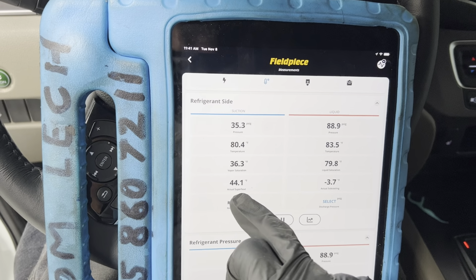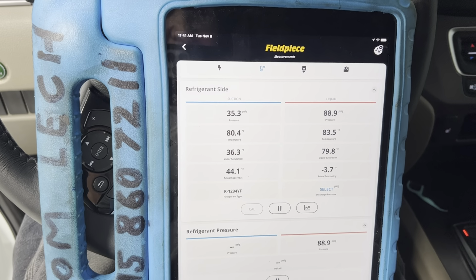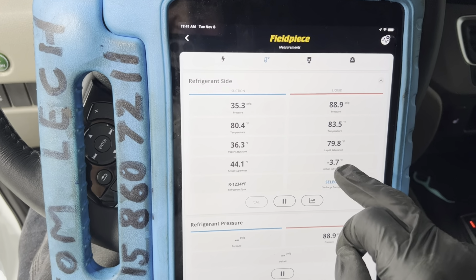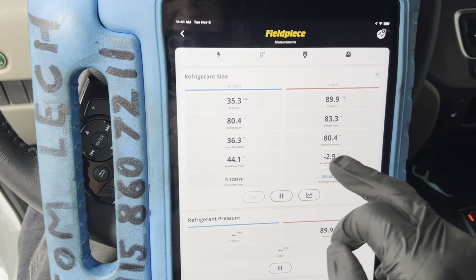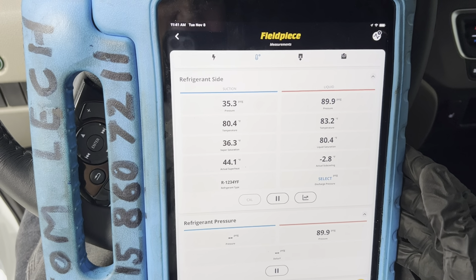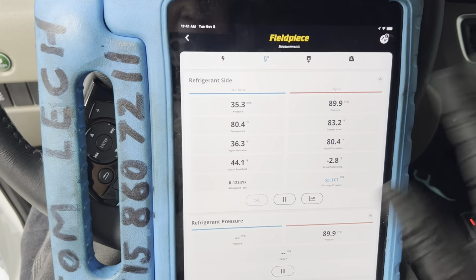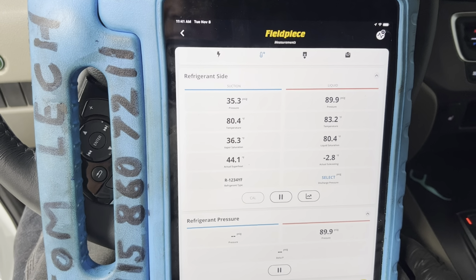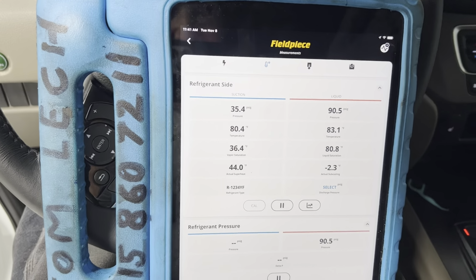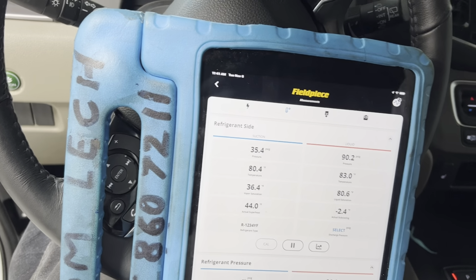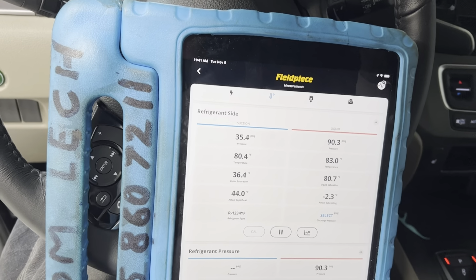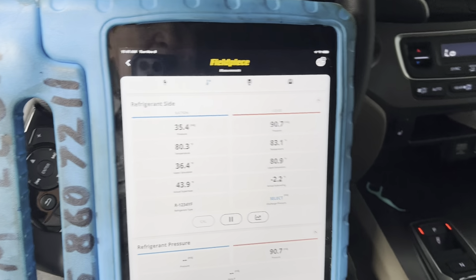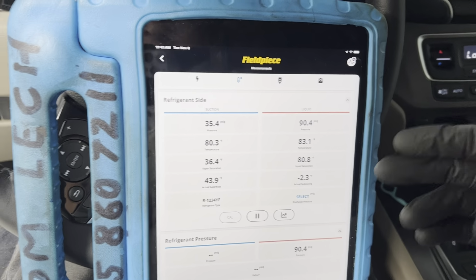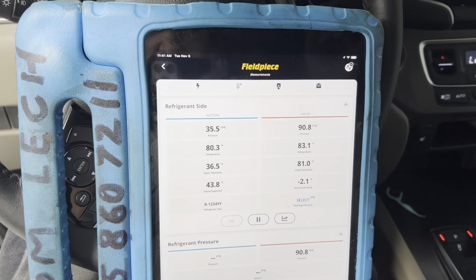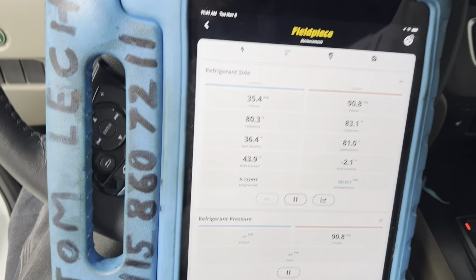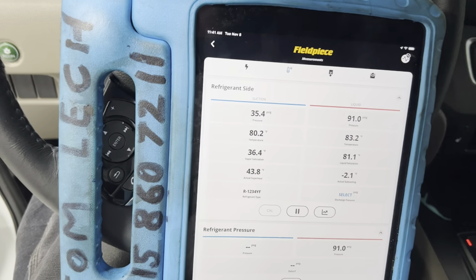So we have superheat at 44 degrees. How do we have a negative 3 subcooling? Every indicator says this thing is starving for refrigerant, but it's a variable displacement compressor, and the ambient temperature sensors are picking up that it's only 60 some degrees outside. The cabin is satisfied, it's really cool. It really messes with your numbers because the compressor is being told what to do by the computer, not by how much refrigerant you keep squirting in.